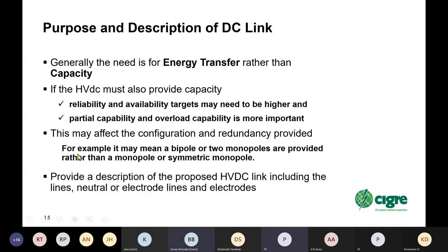So looking at an overall view of the spec, the first thing that you try to describe is the purpose and need for the DC link. And generally the need is for energy transfer rather than capacity. Usually generators are used for capacity, but in some cases an HVDC link can also be considered as capacity in the receiving system.